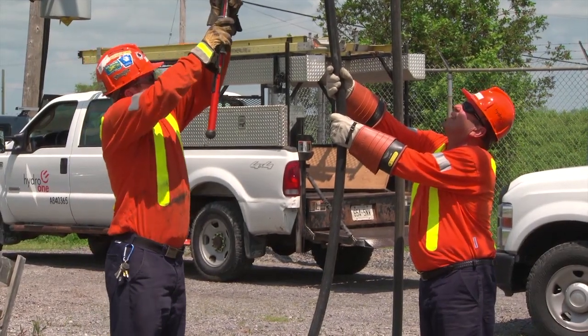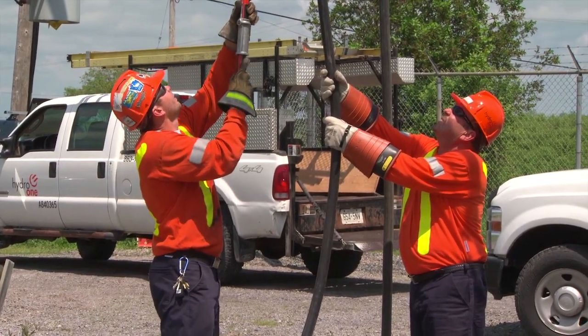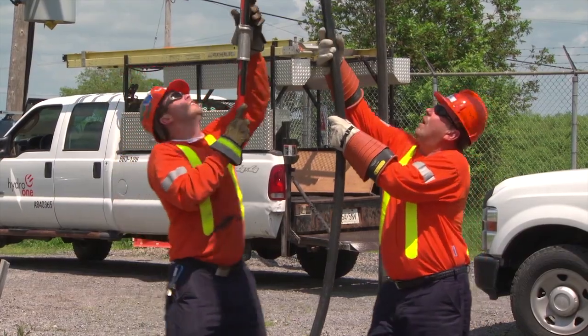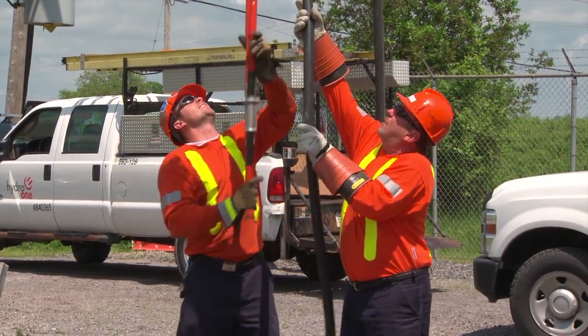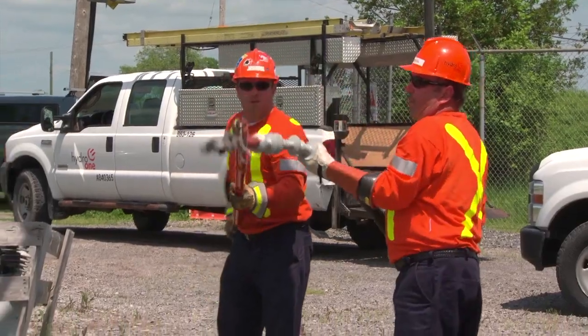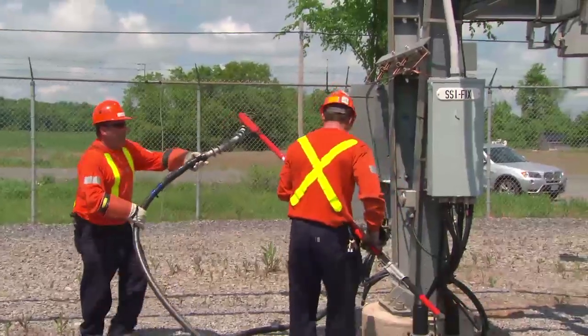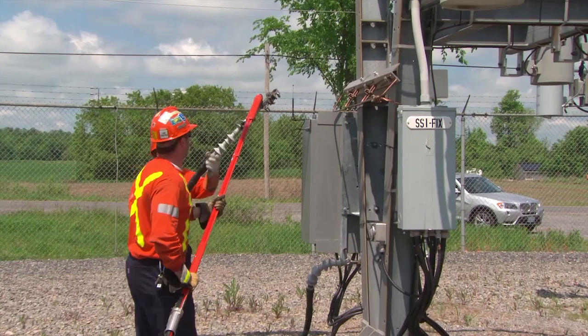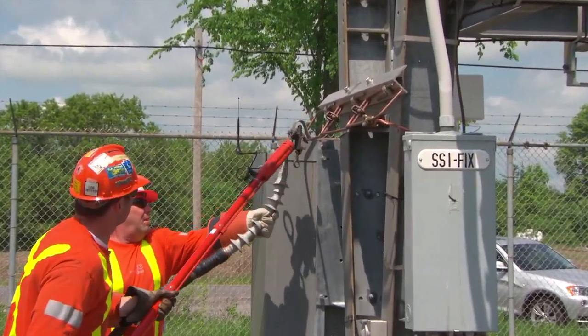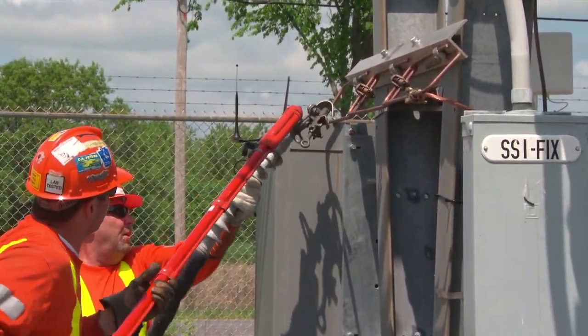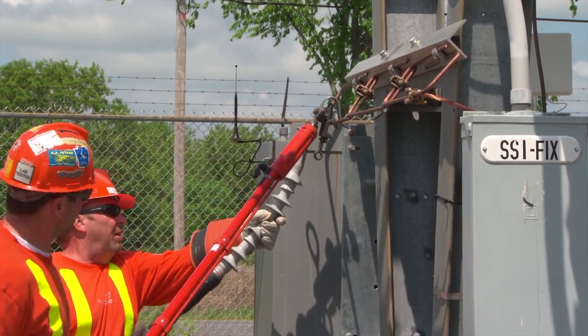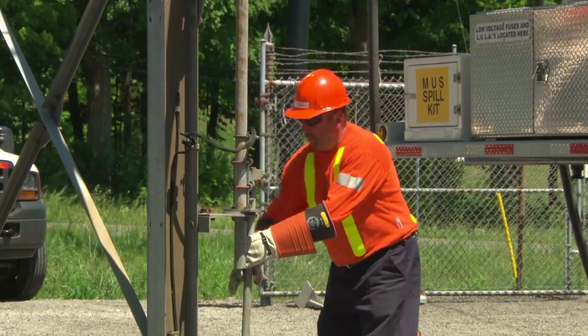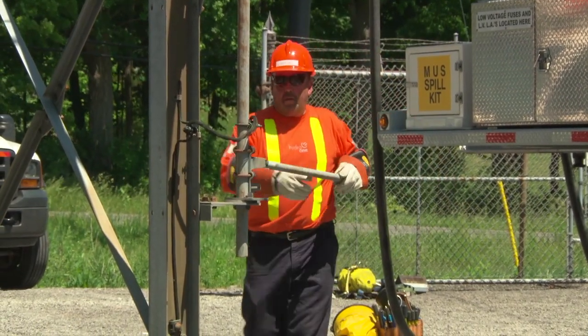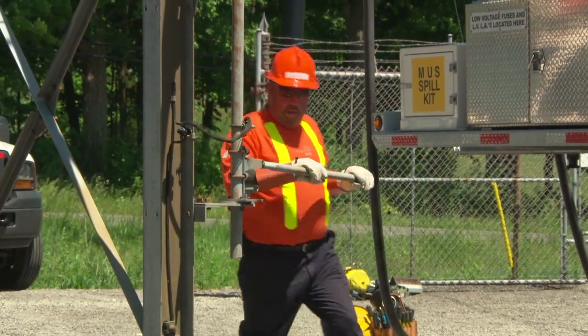Before we look at the installation practices, it's important that you have an understanding of the live line tools you will be required to use throughout the job. Rubber gloves must be worn when handling energized MUS cables. This provides a barrier against induction on the cable or electrical contact should the cable insulation fail. They should also be worn when operating manually operated switches and in damp or inclement weather conditions when operating live line sticks.